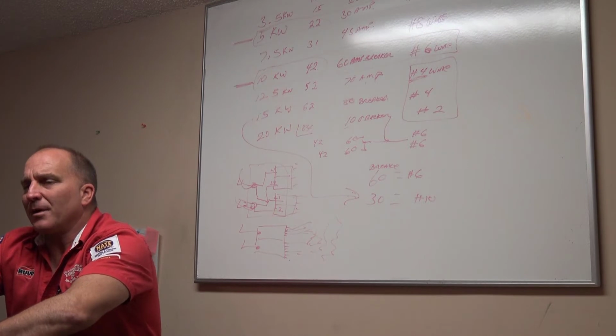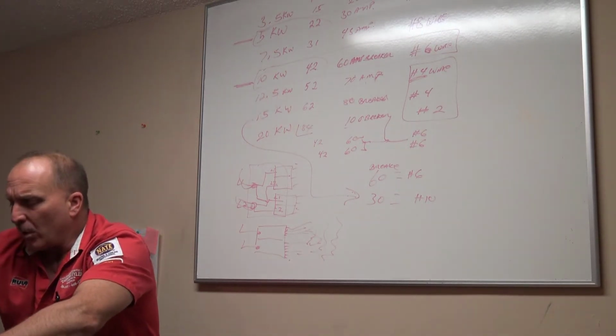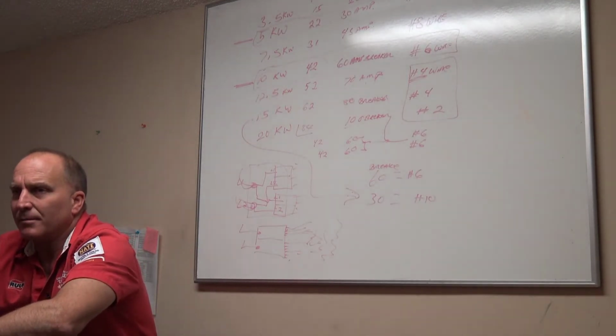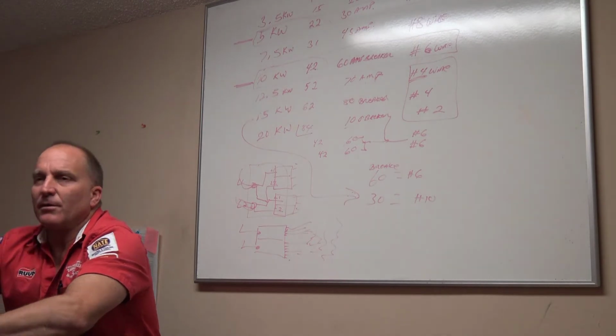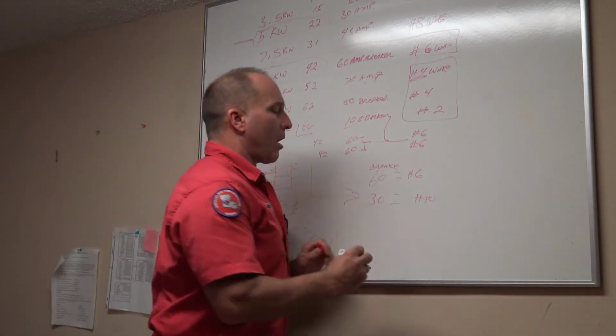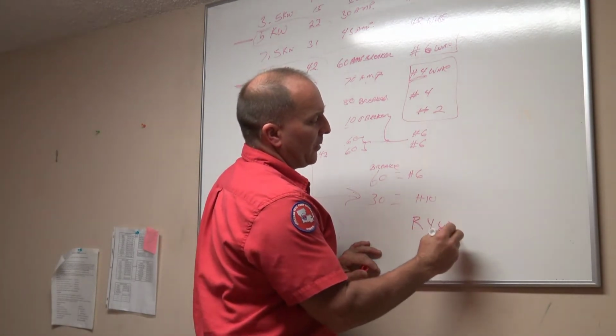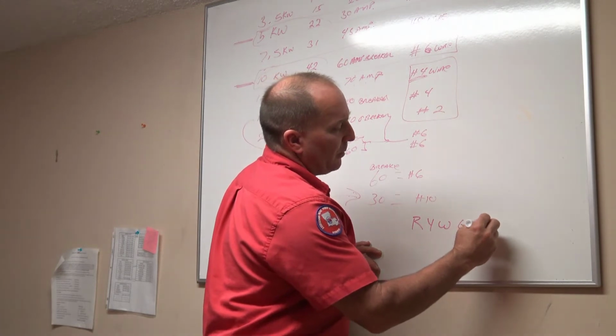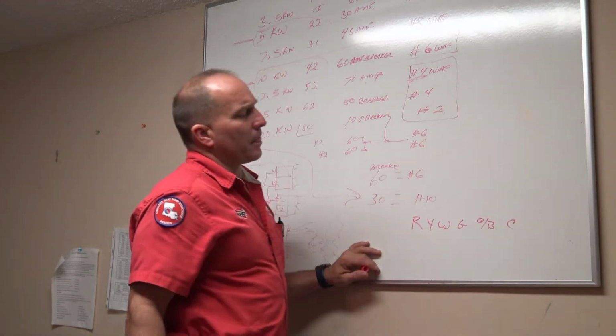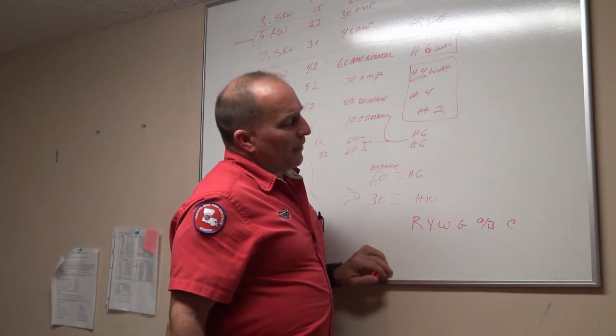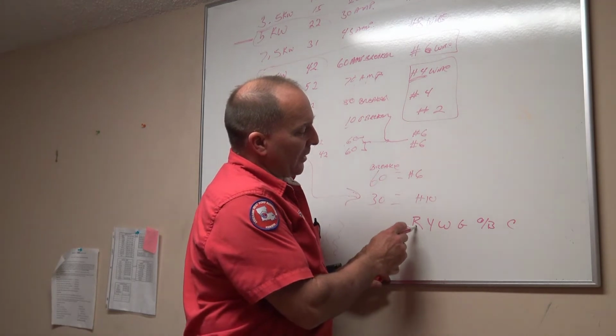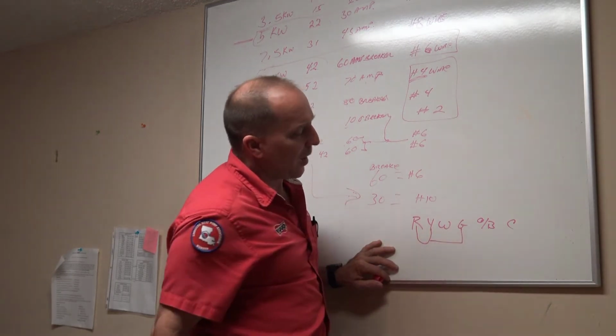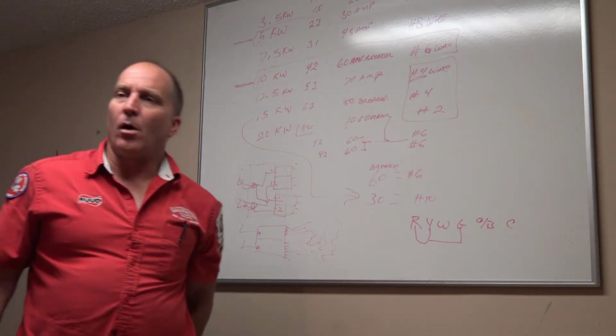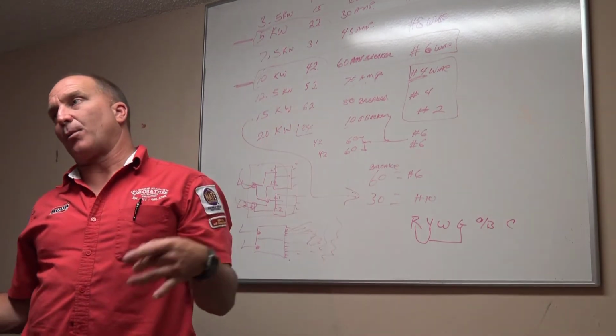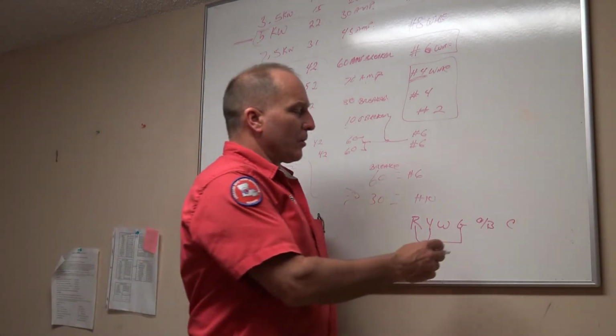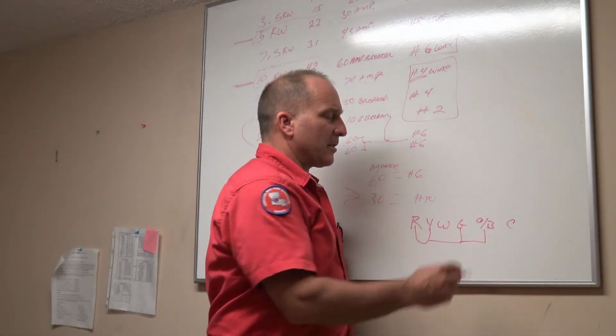So on a heat pump, in case you guys do not know this, especially you new guys, when you turn a heat pump on, what does it energize? The reversing valve. It energizes the reversing valve. So if your low voltage wires are R, Y, W, G, O/B, we'll leave it at that, okay? When you turn a heat pump on in the cooling mode, your thermostat makes a connection between Y and G, okay? On some systems, depending upon that particular brand name and model, sometimes in the cooling mode it also energizes O/B.